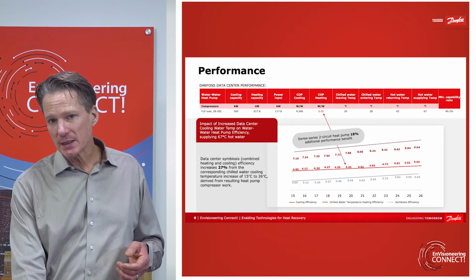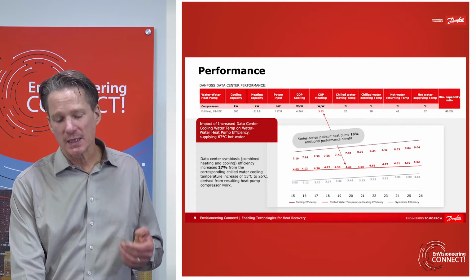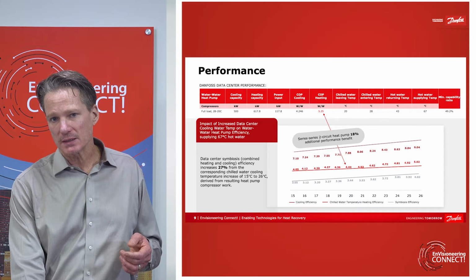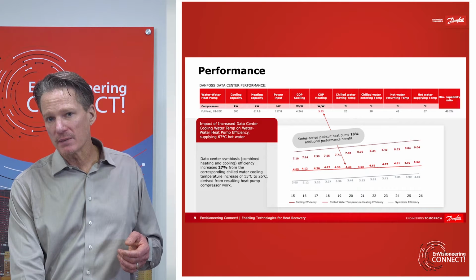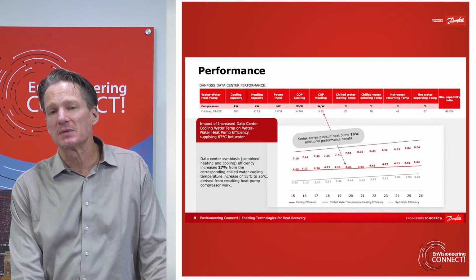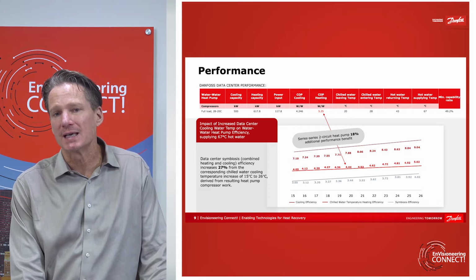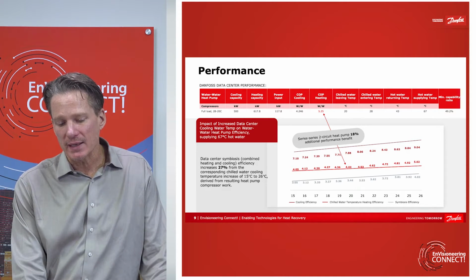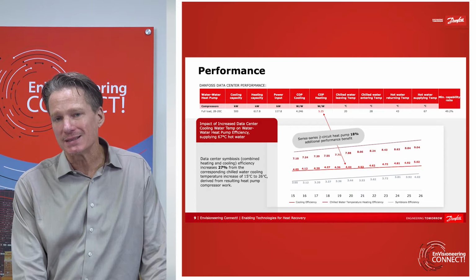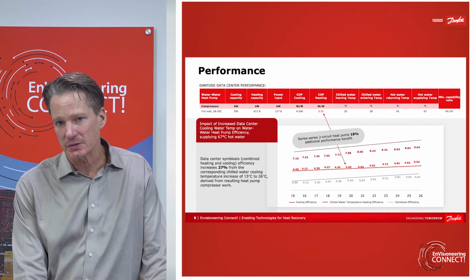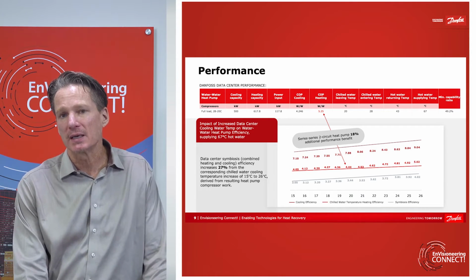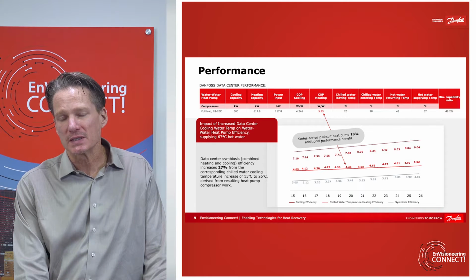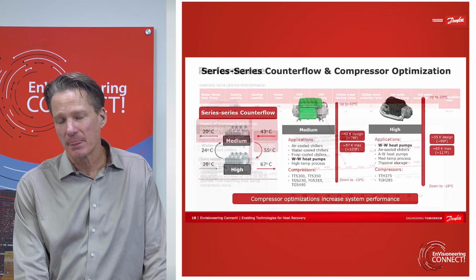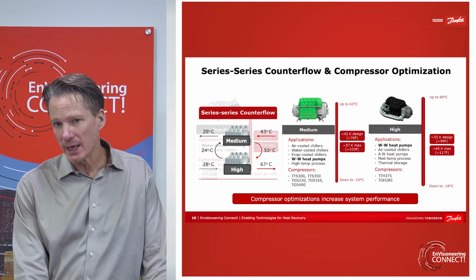And when you do this, and you play with it, from what you see down below in the chart is an individual compressor. What you see up above is the performance of the actual system that was designed for this heat recovery of the data center. And with that, the efficiency is actually about 18% higher than what the individual compressor says it should be at those operating conditions. That's because we can then play with the system design to optimize it to increase the overall efficiency of the water-to-water heat pump system. And this shows how we do that.